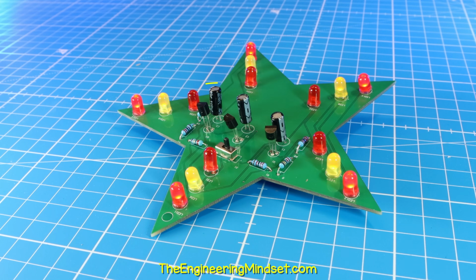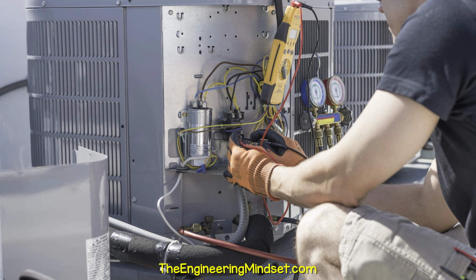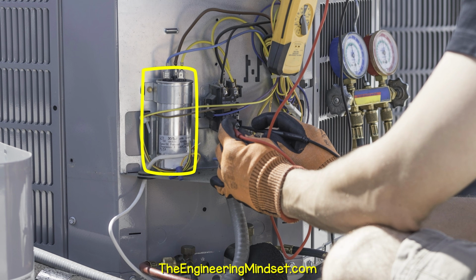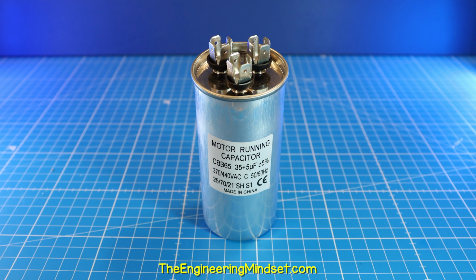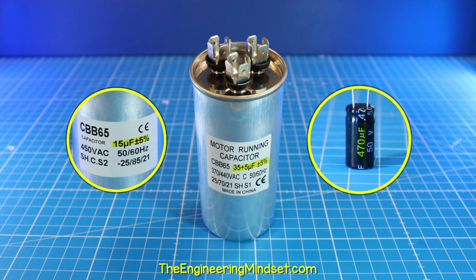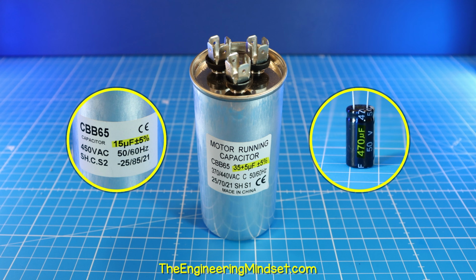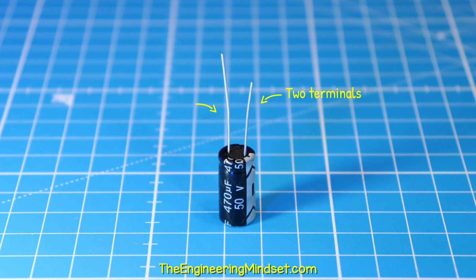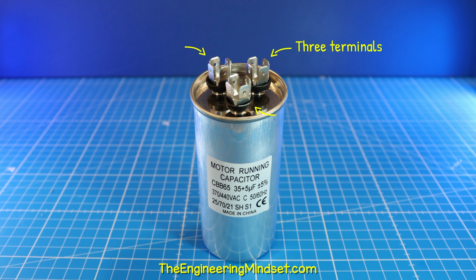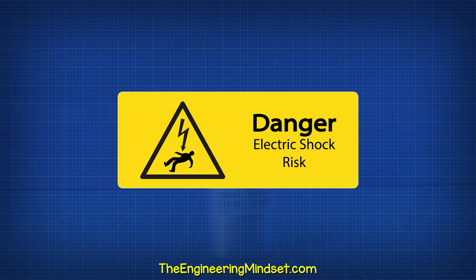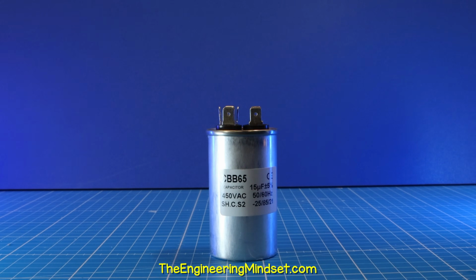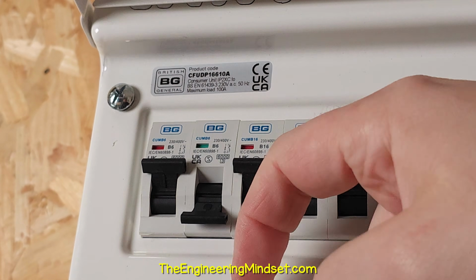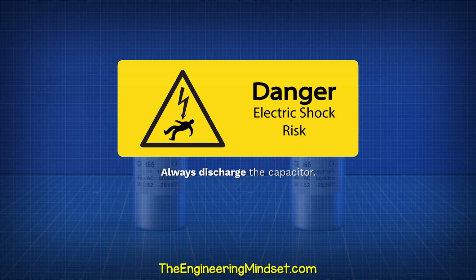We find small capacitors on circuit boards and large capacitors for single-phase motors and fans. The rated capacity is stated on the side, and this is usually in microfarads. These electrolytic and run capacitors have just 2 terminals, but these dual run capacitors have 3 terminals. Do not touch the terminals of a capacitor. They can store energy for a very long time. Always cut the power to the circuit and always discharge the capacitor.